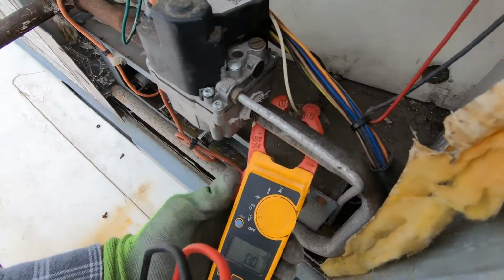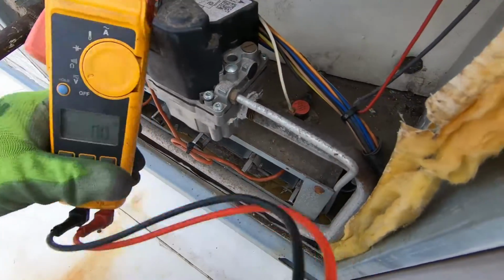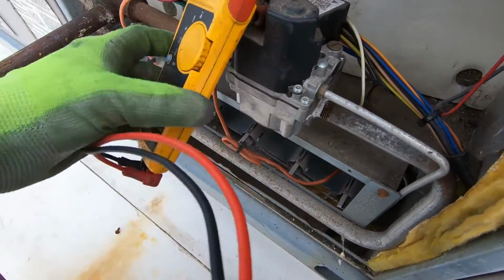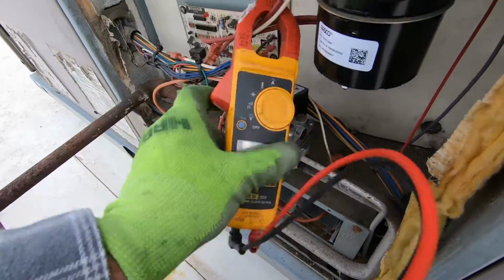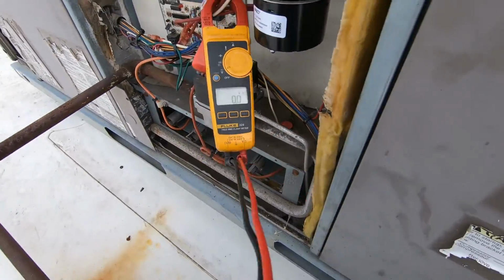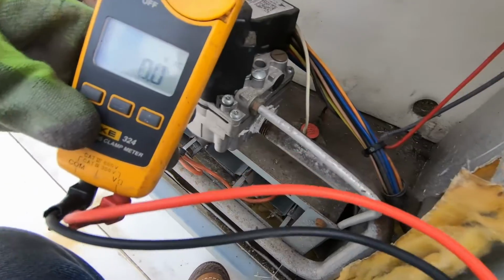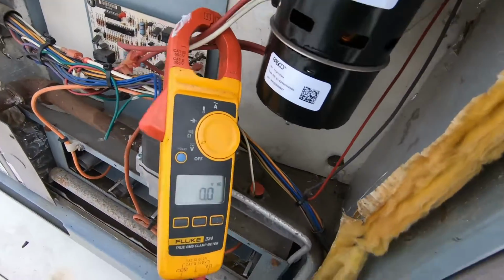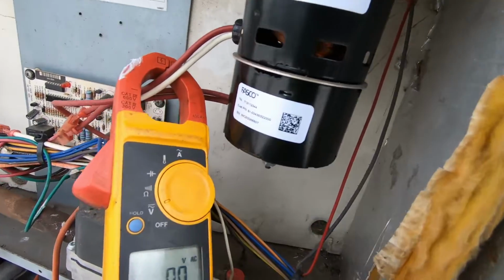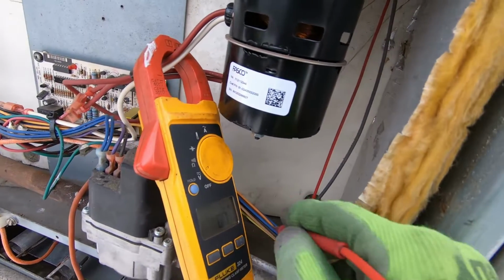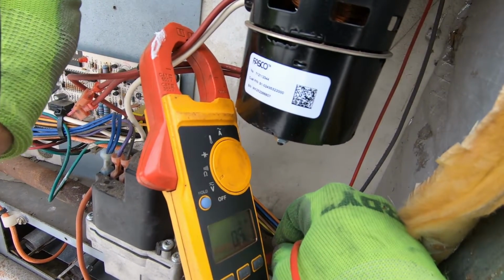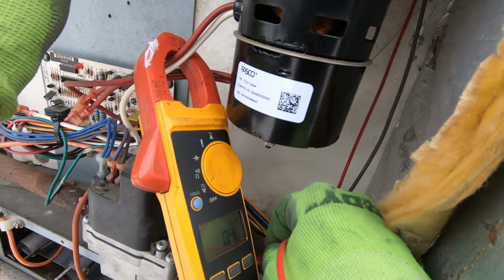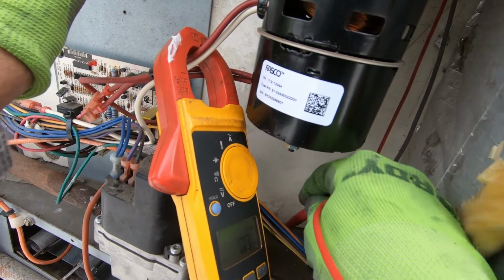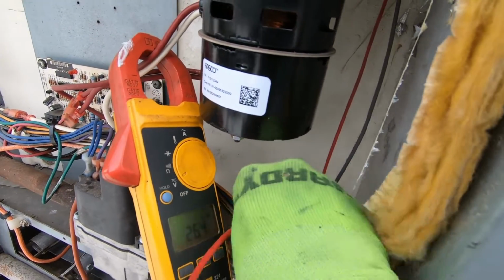It will trip that switch, and it's a resettable switch, auto reset, but I believe if it trips too many times, then it's gonna lock the board out. So we're definitely gonna be checking the heat exchanger on this, checking the blower. But first off, let me check this switch and see if we are open or closed. And I've got, I'm on the sticker, 26 volts on one side, 26 volts on the other. So our limit and our rollout are both closed.